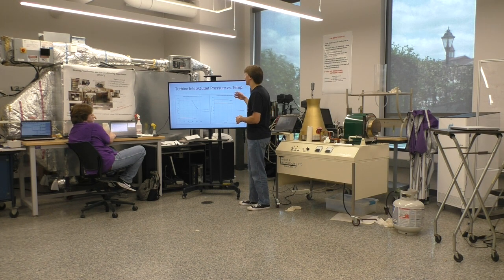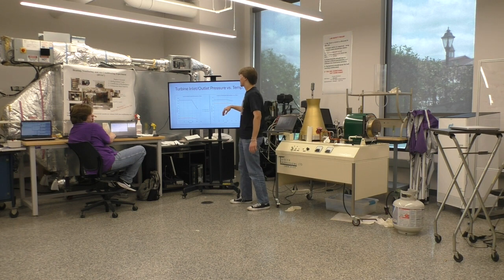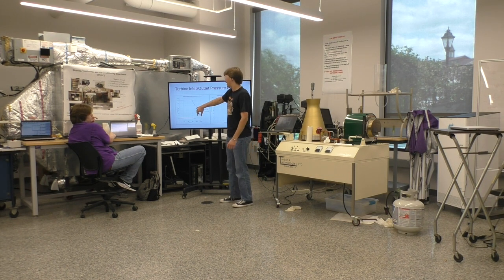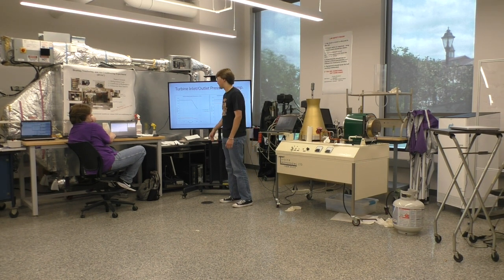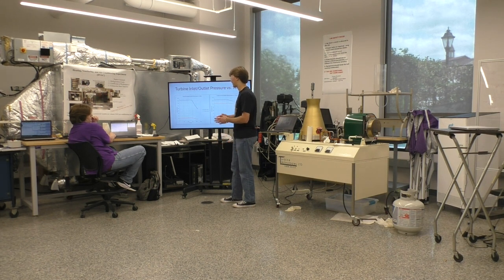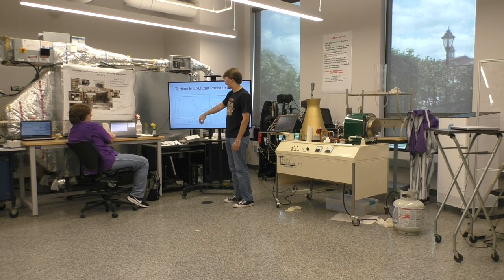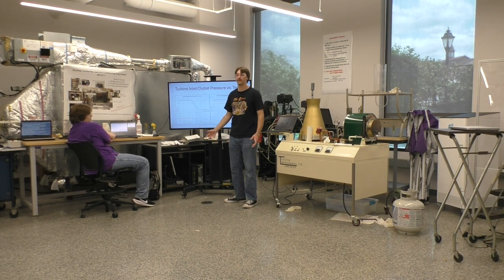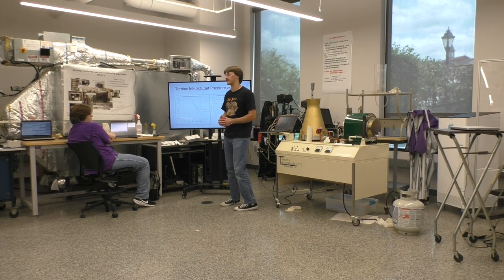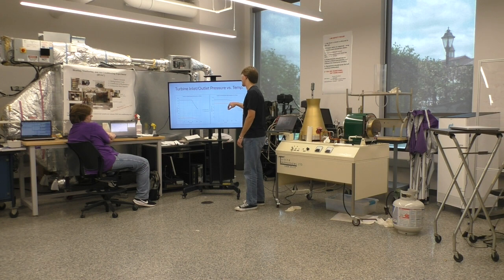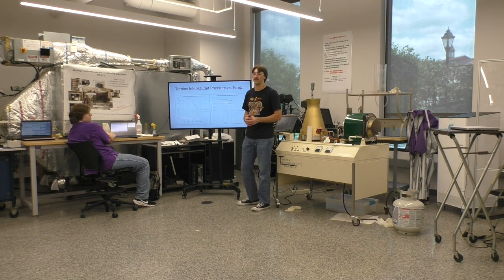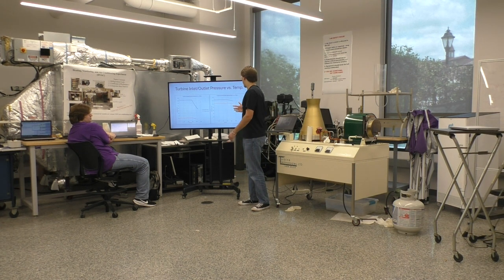turbine. Now looking at the turbine inlets and outlets. Starting with the pressure, we can see that the inlet was able to hold around 163 kPa, which is great. And then as we shut it off, you can see it going down. The turbine outlet was open to the atmosphere, so that's going to stay the same the whole time. And as it shuts off, it's just going to go down slowly.